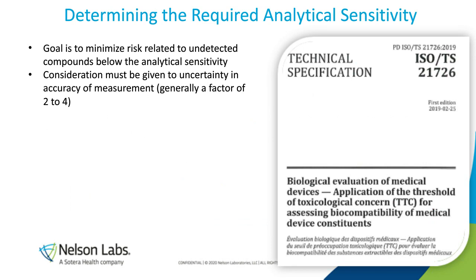In 10993-18, it's called the analytical evaluation threshold. This is the sensitivity that's required for these analyses, so that we know that we're not missing anything that might be really concerning. And this analytical evaluation threshold is based on the TTC concept, which is the threshold of toxicological concern.